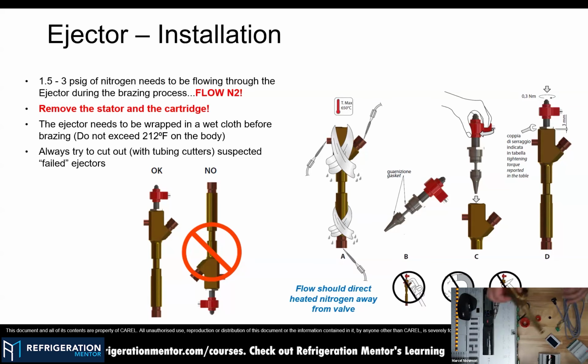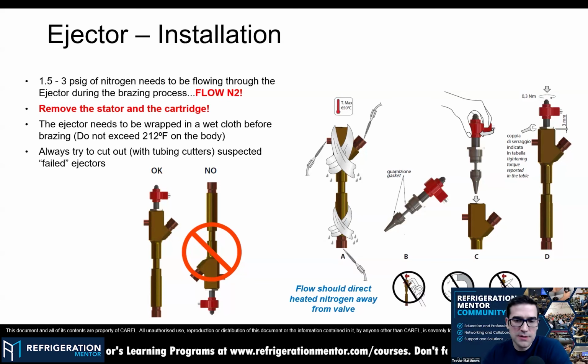Another thing, if you are installing an ejector, is the position. This is more from the OEM perspective on the installation side. You should not install it backwards. You should always install it in a vertical or horizontal position. Okay, so motor up or horizontal. Yep, motor up or horizontal, makes sense.